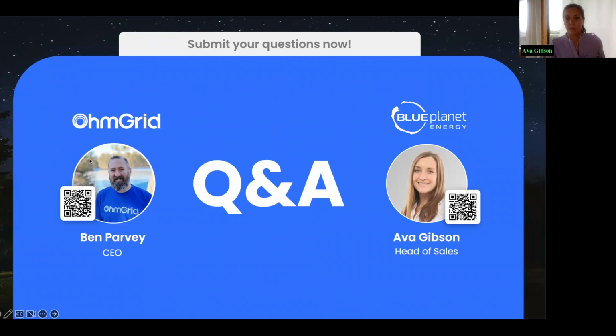Now jumping into your next question on expandability: each enclosure has a BMU rated at 8 kilowatts of continuous power, so the smallest system size we can do is 8 kilowatt hours per enclosure. That's because we have a 1C charge and discharge rate, so we can't do a 4 kilowatt hour increment in just one enclosure. What we could look at is shifting part of the 16 kilowatt hour first system to the second enclosure so you'd have 12 and 8. But preferably we'd have at least 12 and 12, and then you can fill out in 4 kilowatt hour increments after that. I hope that makes sense.